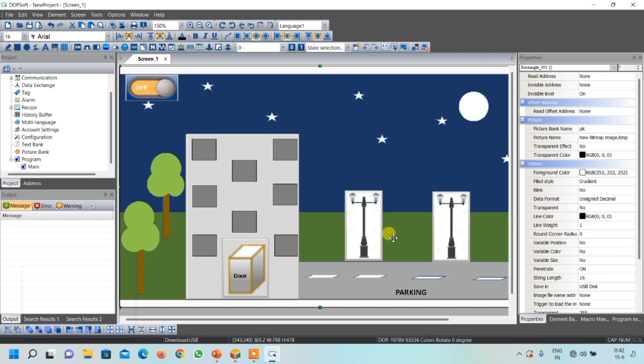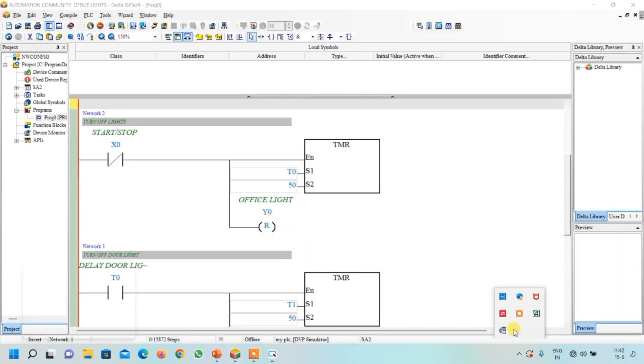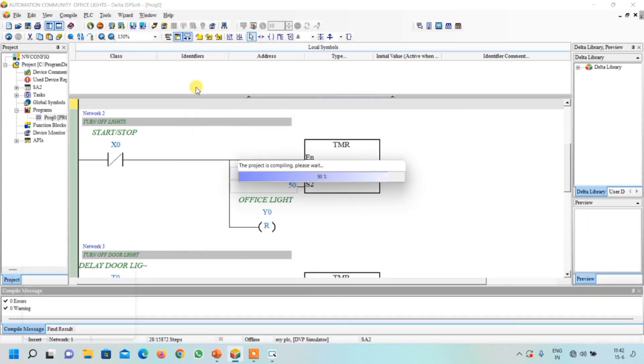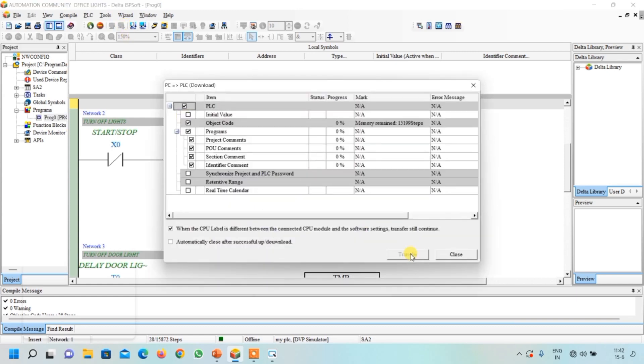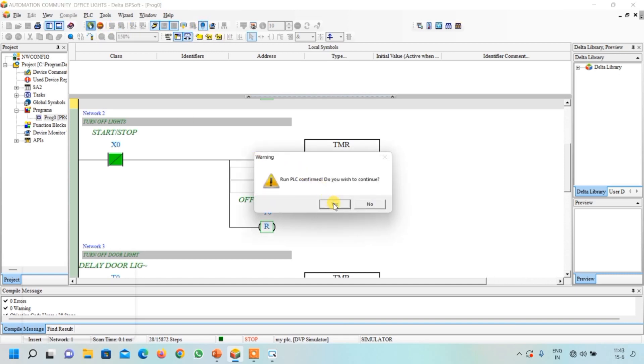HMI designing is now complete and it is time to simulate the project. Open your ladder diagram programming in ISPsoft, then open COMGR and start your simulator — it is already in start position so just close it. Compile the project, and once there are no errors or warnings, click to download the program to the simulator and click the Transfer button. Close the box, click Online Mode, turn on the bit, and click Run. Click Yes and the simulator has started. Now open DOPsoft HMI and click Offline Simulation.